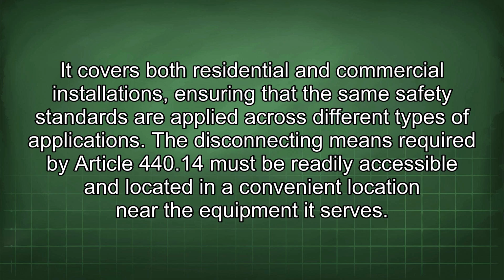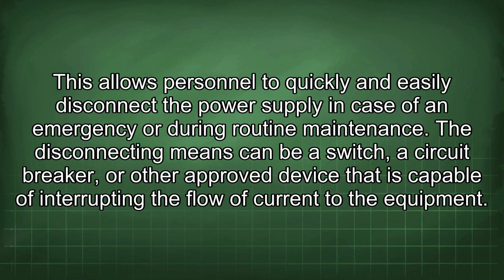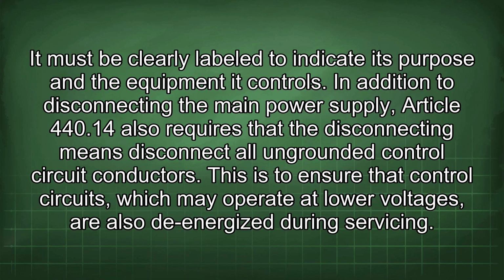The disconnecting means required by Article 440.14 must be readily accessible and located in a convenient location near the equipment it serves. This allows personnel to quickly and easily disconnect the power supply in case of an emergency or during routine maintenance. The disconnecting means can be a switch, a circuit breaker, or other approved device that is capable of interrupting the flow of current to the equipment. It must be clearly labeled to indicate its purpose and the equipment it controls.